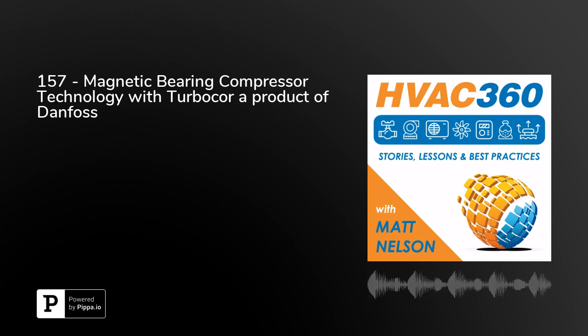Now, when somebody's selecting a Turbocor, is it specific manufacturers, or can they mix and match or specify that a certain manufacturer use Turbocor? Well, whenever somebody's trying to use Turbocor, we have a set of OEMs that we work with. Turbocor is a technology, and an OEM has to build their chiller around the technology. So we work with a limited number of OEMs. Those are all listed on our website, the OEMs that currently offer Turbocor products. So if they were specifying a Turbocor based chiller, they can identify which OEM they would want to work with.